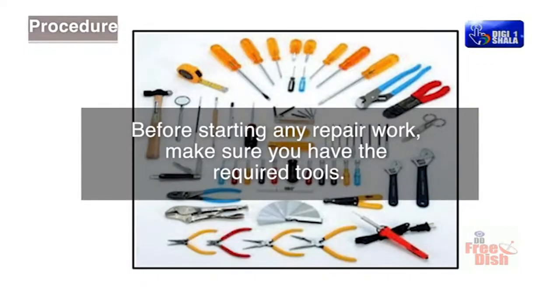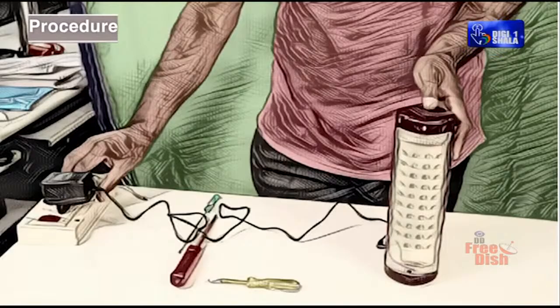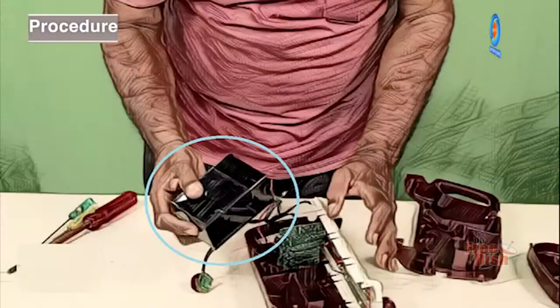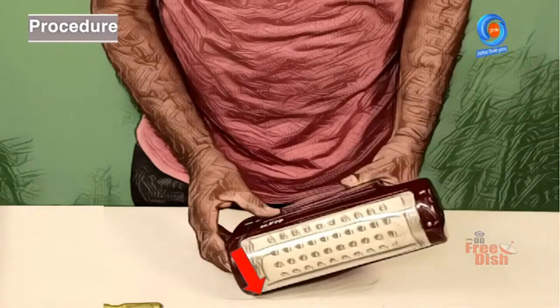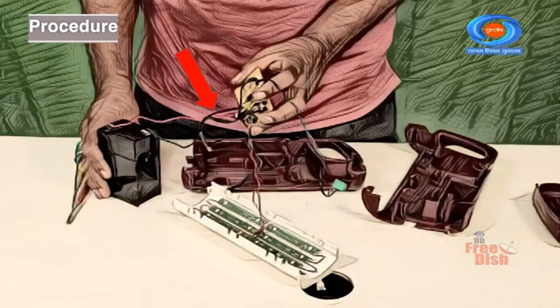Our next task is to repair and maintain the emergency light with the help of troubleshooting sequence block. Before starting any repair work, make sure you have the required tools. Ensure that the emergency light is disconnected from the power source to avoid any electrical shocks. If it has a battery, remove it as well. Check the emergency light for any visible physical damage, loose connections or burnt components. Look for broken wires, loose screws or any signs of overheating.